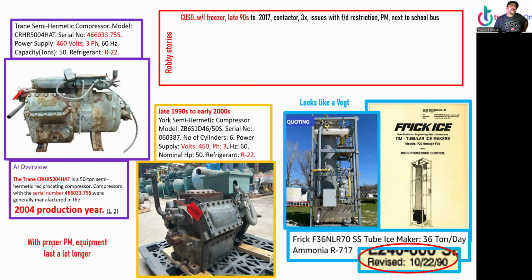a long time ago, we installed a walk-in freezer in the late 90s. And over the years, I replaced the contactor 3 times. We had an issue with the filter dryer restriction later on, but we did PM every year. It's next to a school bus, and the school bus parked there, and so much dirt got on that condenser. But as long as you do PM, it's still working. Finally they took it out in 2017 and put in a new system because it's more efficient and saves money.